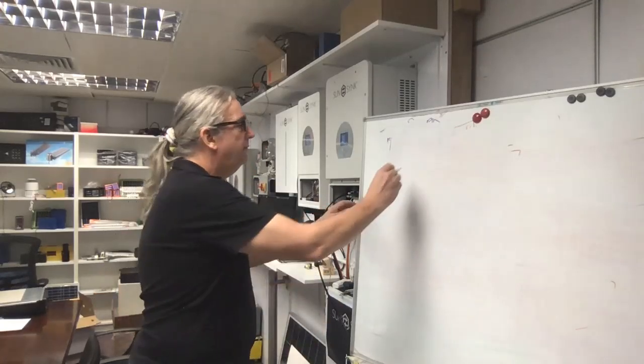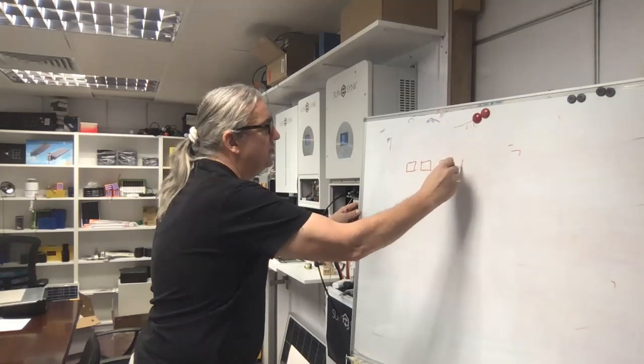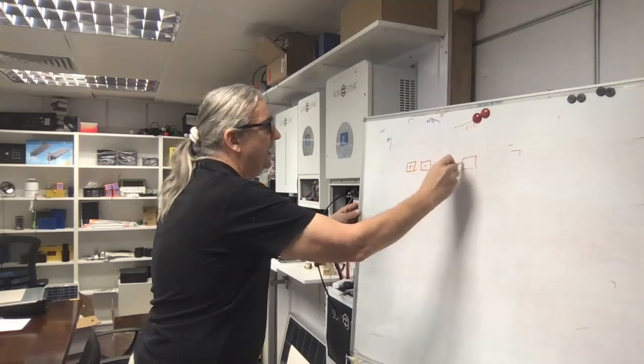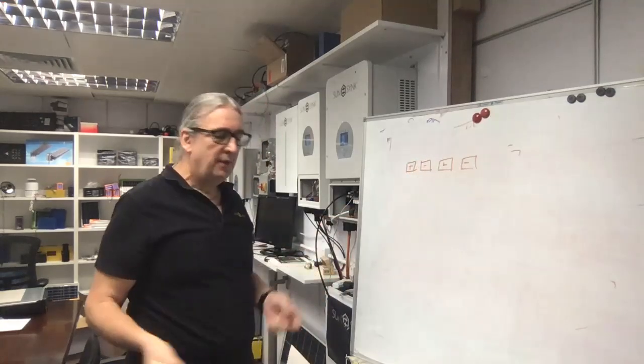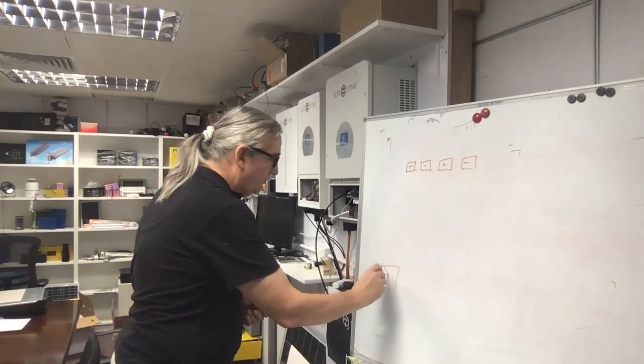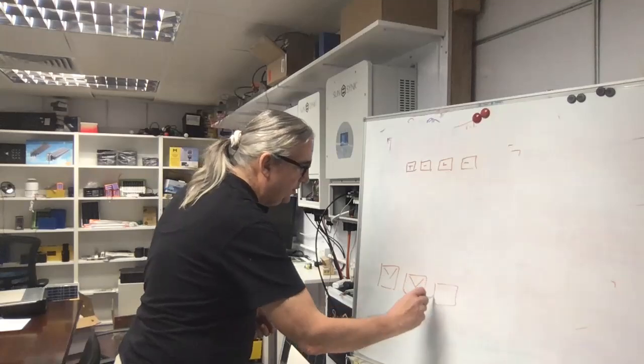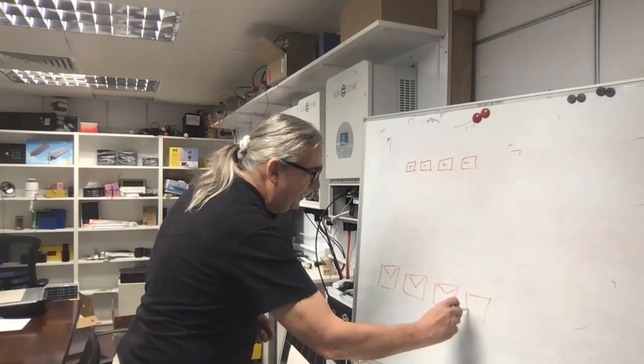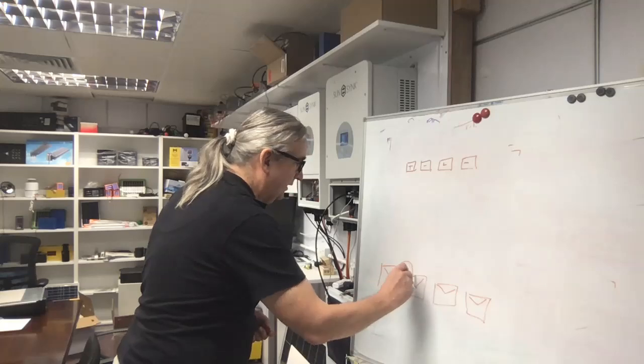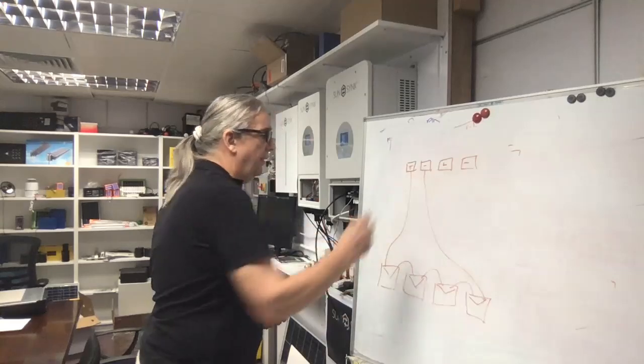Very simple, I've got four connections. There's two MPPTs: plus negative, plus negative. I get my string of solar panels in standard 320 watt, 72 cell. Roughly nine solar panels can connect together, slightly depends on the panel, and that will go into there.